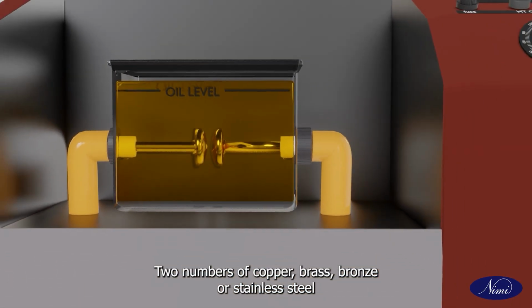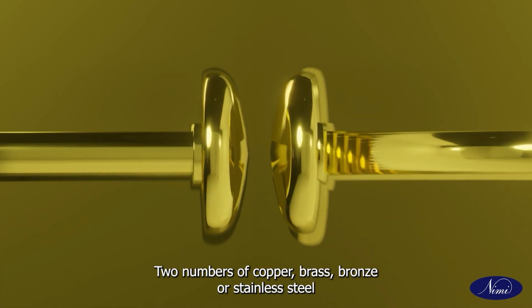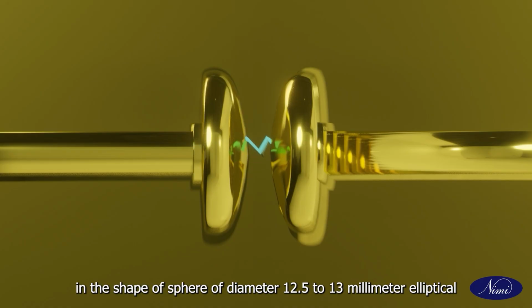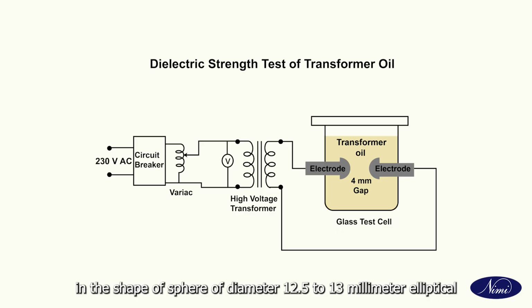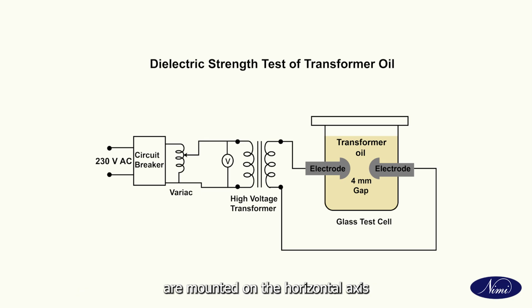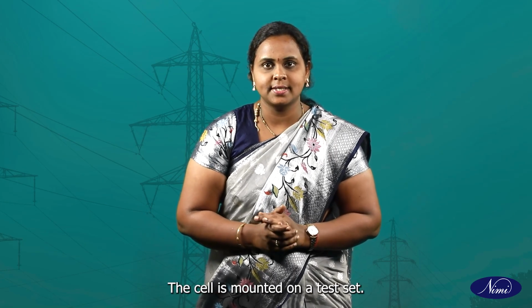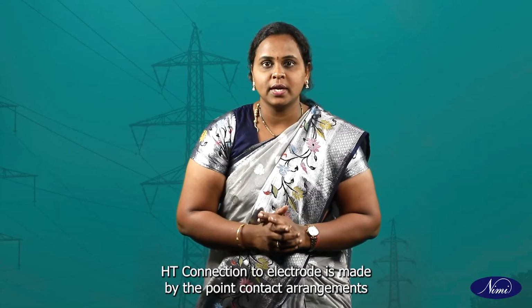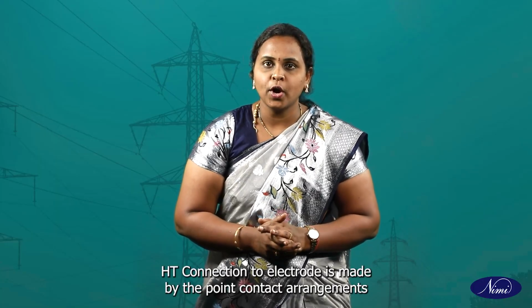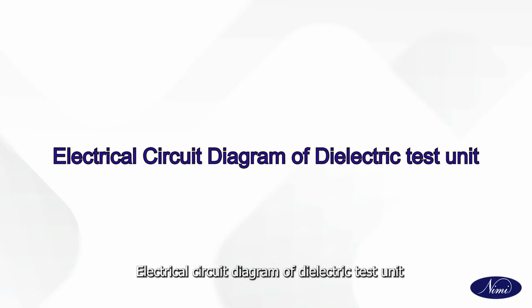Two electrodes of copper, brass, bronze or stainless steel, in the shape of spheres of diameter 12.5 to 13 millimeter, are mounted on the horizontal axis 2.5 millimeter apart and are used as electrodes for the oil test of an 11 kV transformer. The cell is mounted on the test set. HT connection to the electrode is made by the point contact arrangements. Electrical circuit diagram of dielectric test unit.